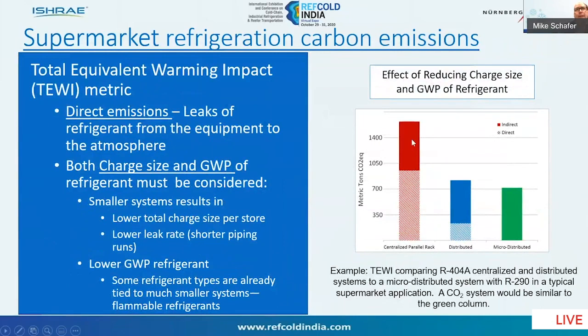So when we look at the direct emissions, we're looking at the leaks of the equipment. So we want to be cognizant of the charge size and the GWP. Certainly smaller systems will reduce the overall charge, and then the smaller systems by definition would have shorter piping and a lower leak rate. And then obviously we want to choose the lowest GWP refrigerant as possible, and some architectures are once again more suited for that.